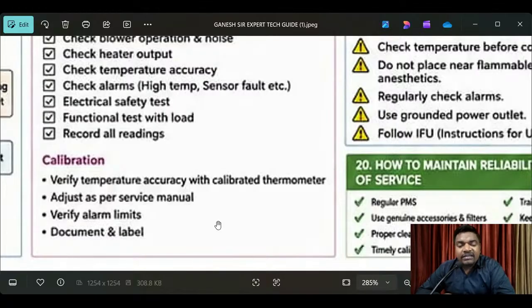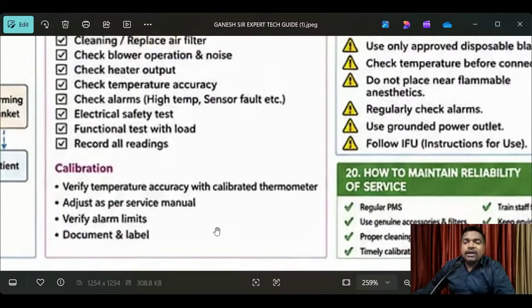We consider the parameters available in that medical equipment. Those parameters are continuously used when we connect the patient for patient monitoring. For those parameters to be accurate, we have to calibrate the medical equipment using master test equipment. Okay, master calibration equipment is different and very expensive. By doing this we can maintain good reliability of our services for all medical equipment. Okay, that is the great responsibility of a biomedical engineer, right? I hope it is very clear. Do you know what I have explained? You got it?